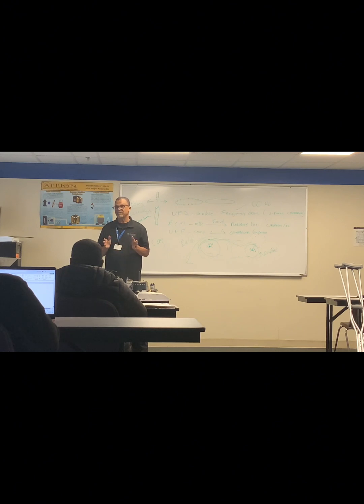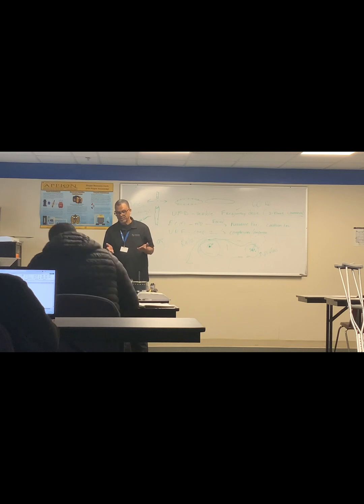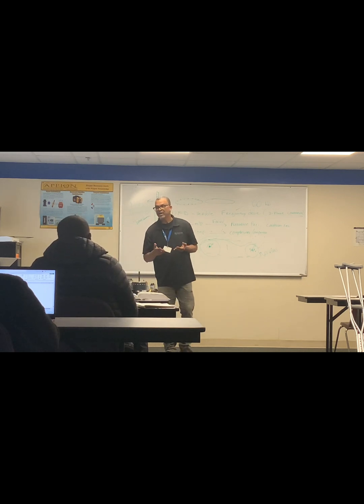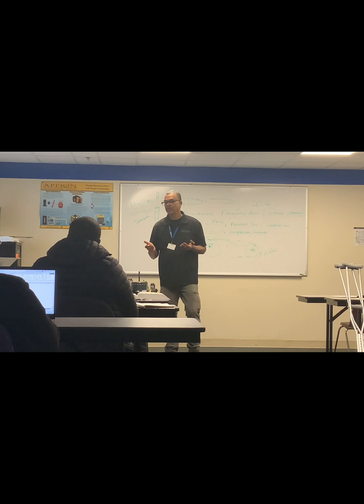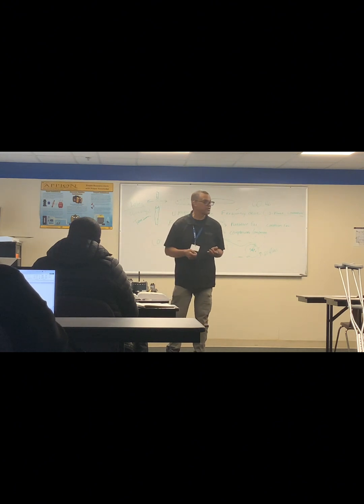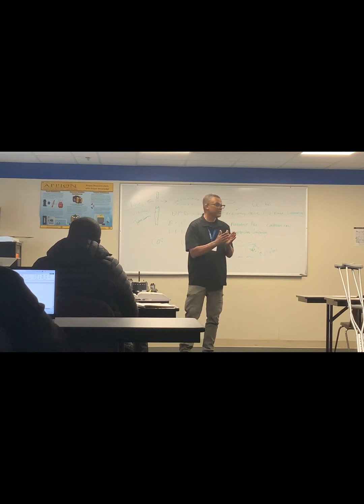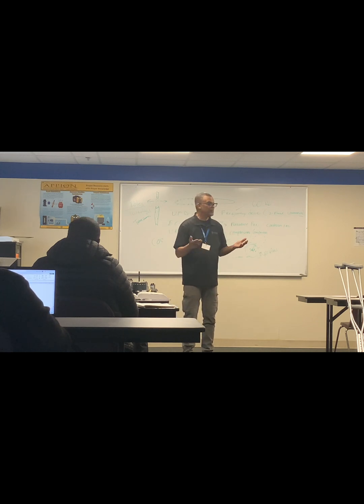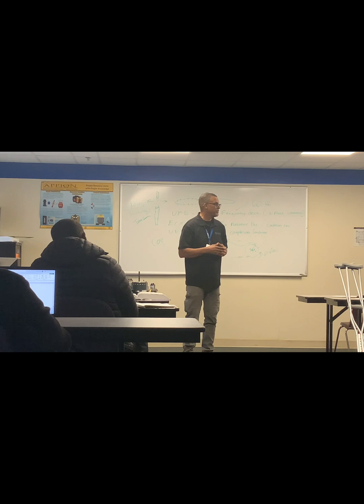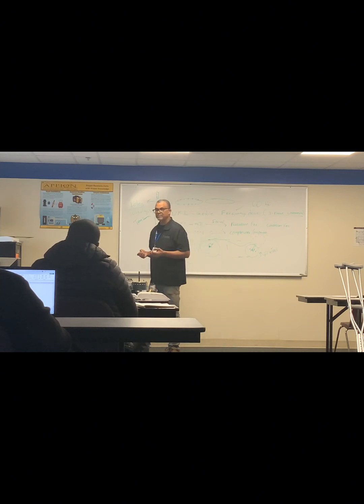They look the same. So you go on a job and you'll be trying to change this and change that, and you have to say it's a 24 volt system and look at the side of that contactor, and that contactor tells you 120 volts. That means somebody before you pulled that part off their truck because it looked the same, and put it on there and couldn't figure out why it didn't run, because it doesn't have 24, it needs 120 volts to run. Some of those contactors can be used on commercial equipment. They look exactly the same.